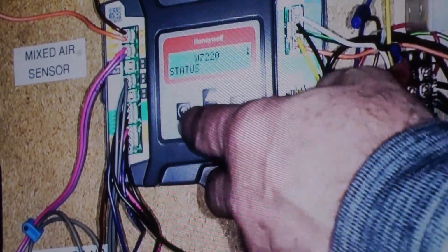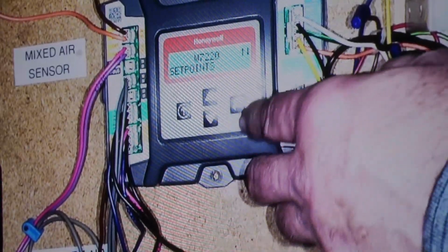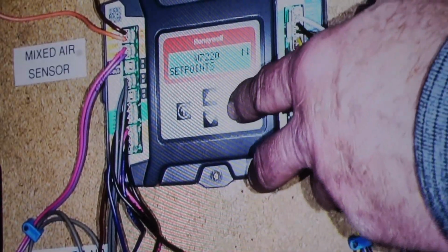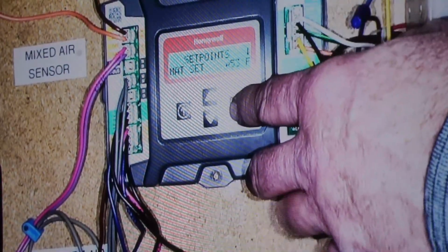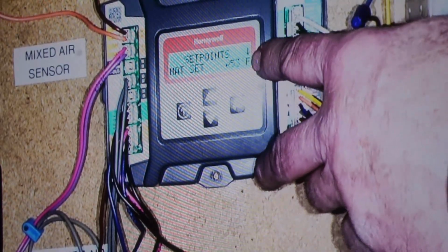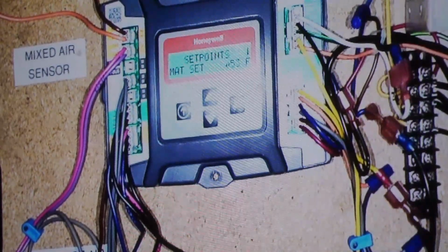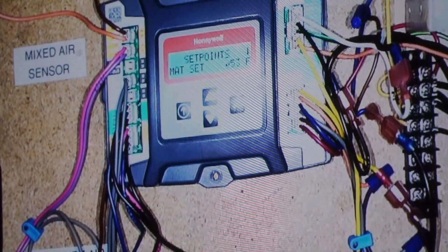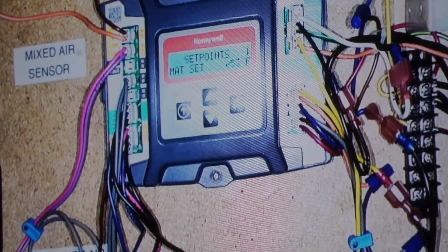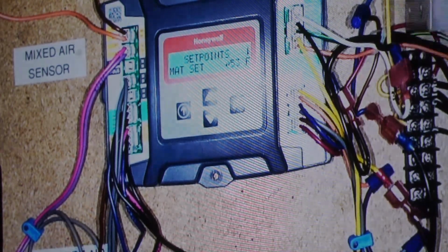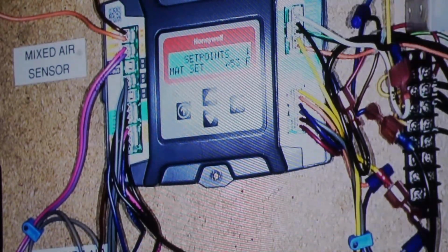The next menu is my set points. This is the next critical menu when you're setting up a unit, obviously. Mixed air temperature set point is 53. That's what those dampers are going to modulate to maintain. And remember, a couple degrees of motor heat, fan heat, we're going to get 55 in the space. That's critical because more is not better.